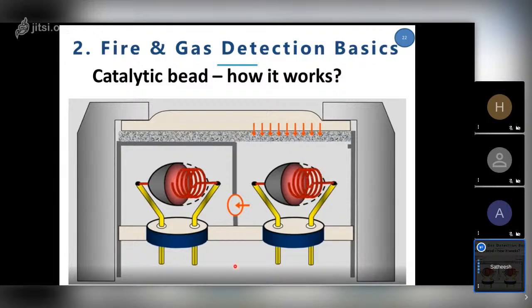And you know very well about the Wheatstone bridge, being instrumentation professionals. So these beads are connected to the Wheatstone bridge arms to generate a millivolt or milliampere electrical signal proportional to the gas concentration. One bead is exposed to the gas, one is non-exposed. This bead is used as a reference bead, because if there is any issue with the ambient, like humidity or temperature, and the resistance is changing, there will be an equal change. That way we can compensate for the losses due to factors other than the gas itself.